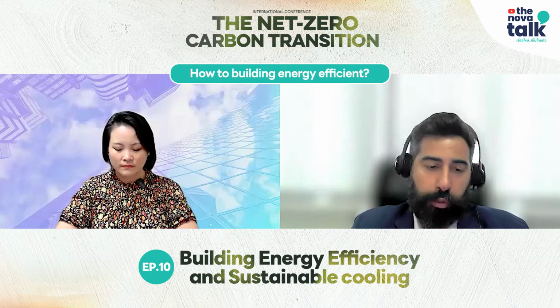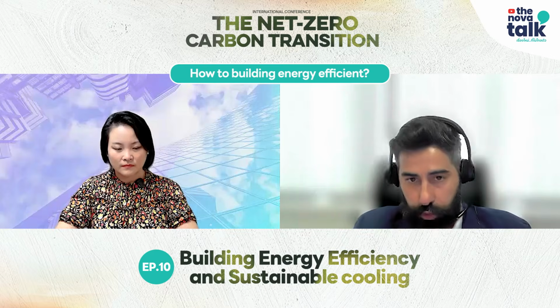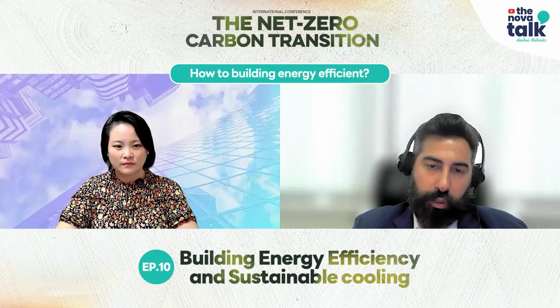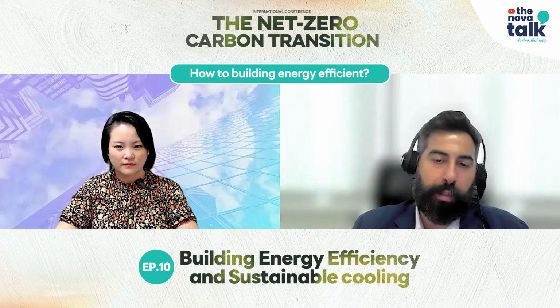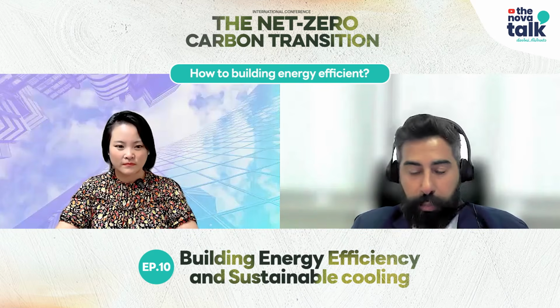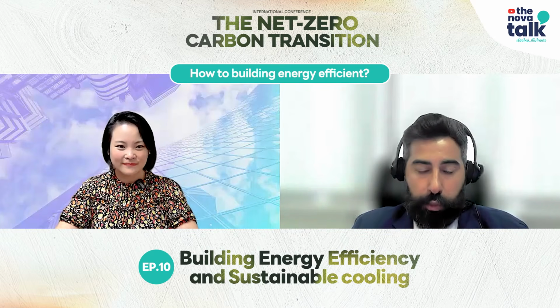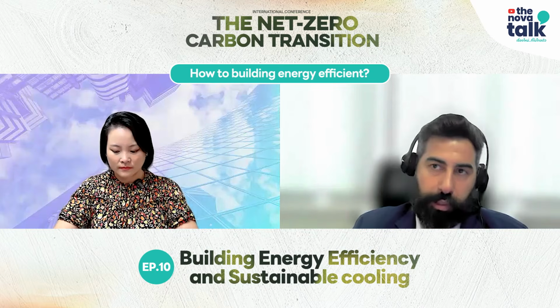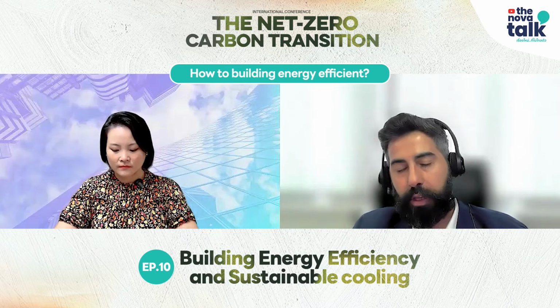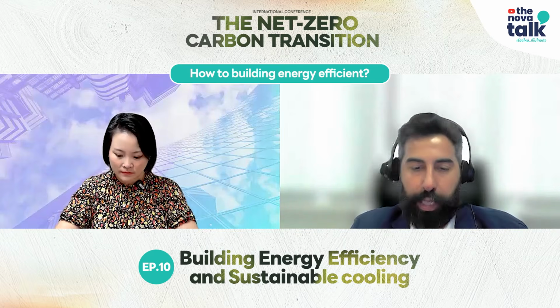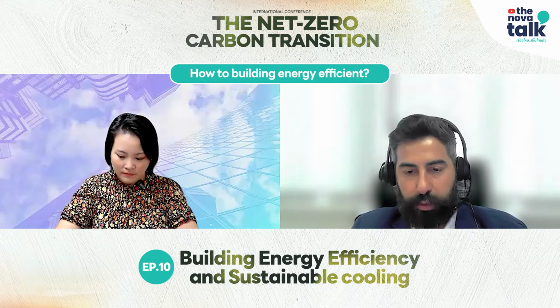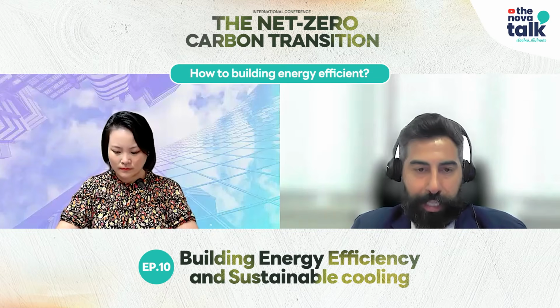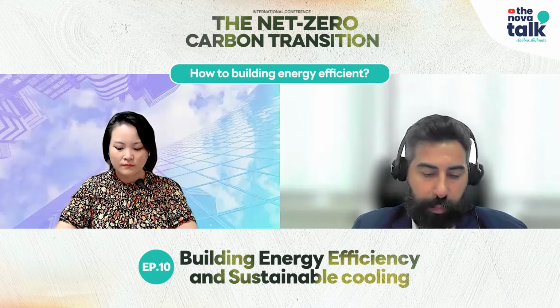And then we have the choice of going with air-cooled chillers or water-cooled chillers. Water-cooled tend to be more efficient because we're using the wet bulb rather than the dry bulb in determining the heat rejection temperature. And then, if we're using water-cooled chillers, we need to have condenser pumps and we need to have cooling towers. And again, we need to size the cooling towers appropriately to reduce the lift on the compressors, which is basically the difference between the pressure of evaporation and the pressure of the condenser.